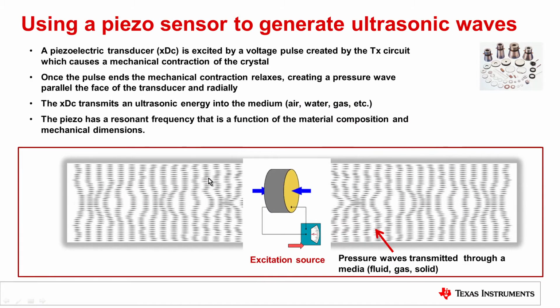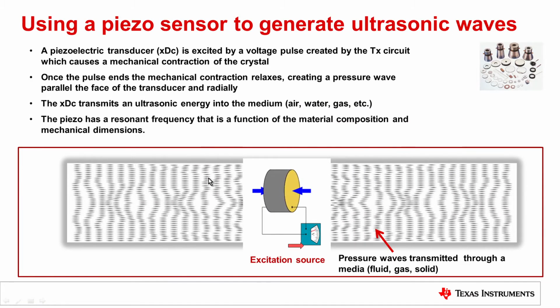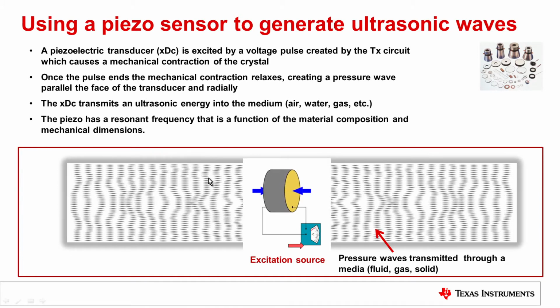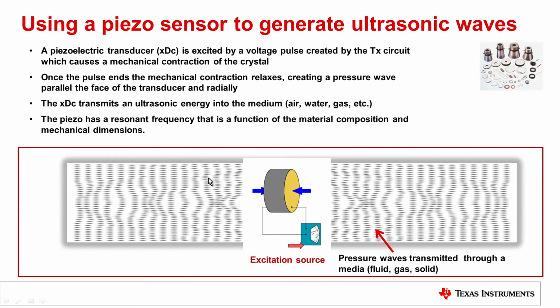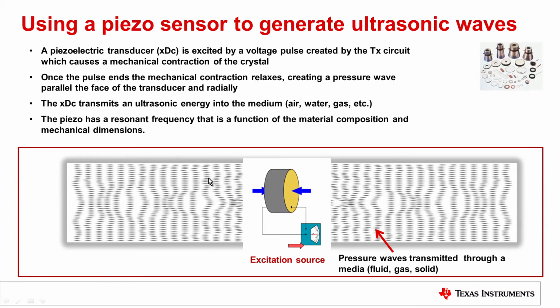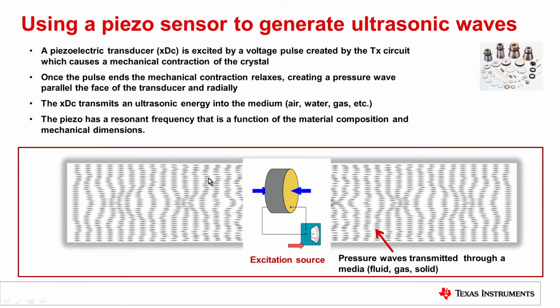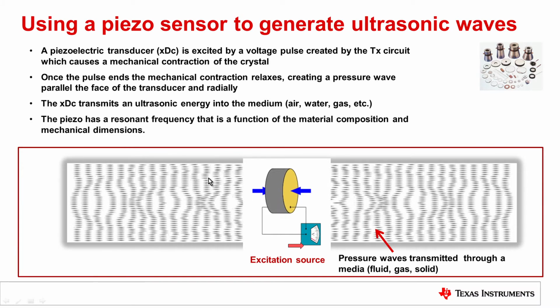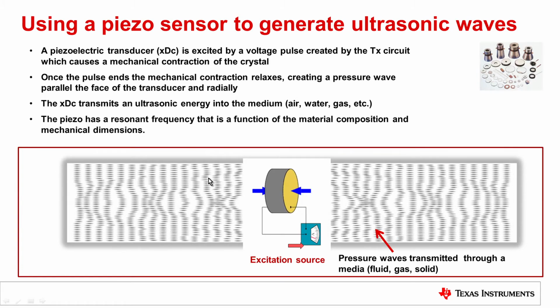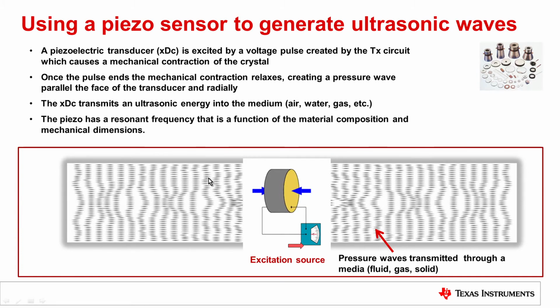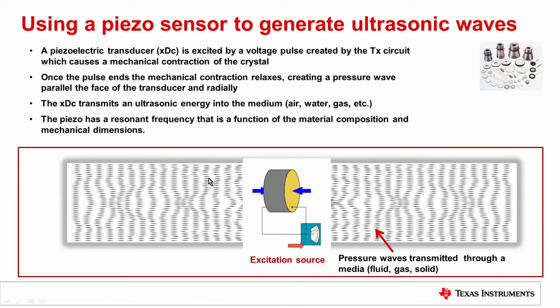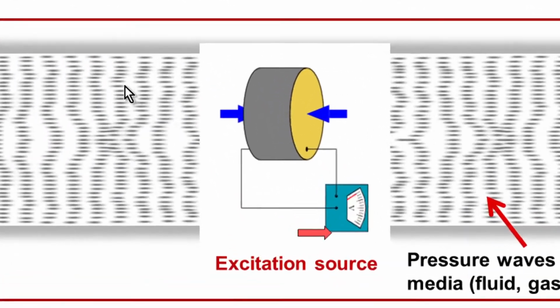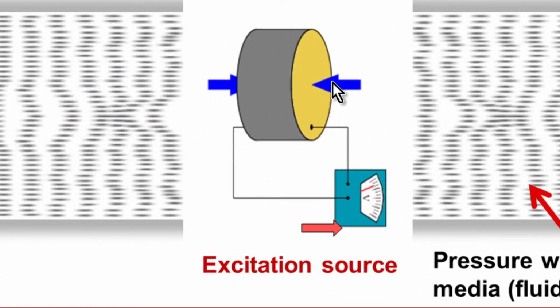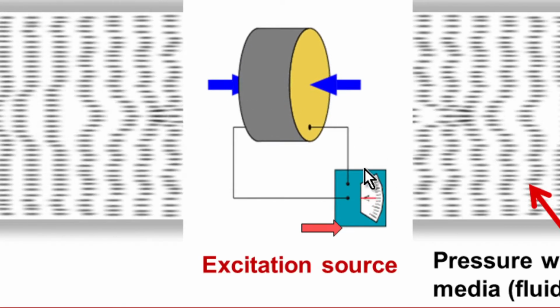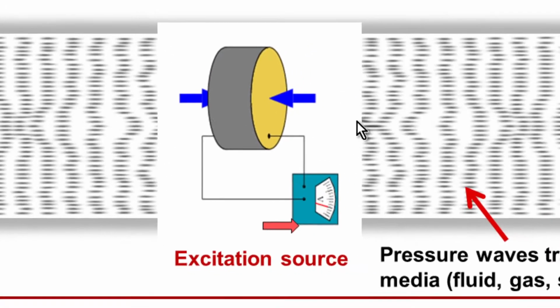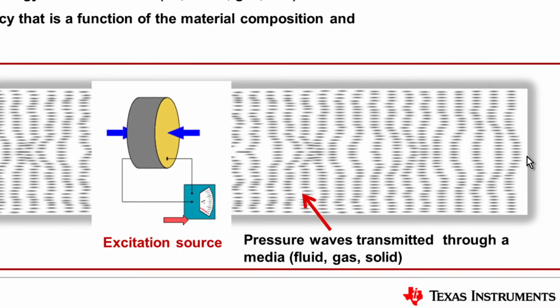Talking a little bit more about transducers, how do transducers work? Transducers are ceramic crystals that when you apply a voltage to them, they contract. Once that voltage is removed, that contraction stops and the expansion creates a pressure wave in the material that it's connected to. In this diagram here, we can see as the voltage is applied, the crystal contracts when there's a voltage present. That pressure wave then moves through the material to the boundary.